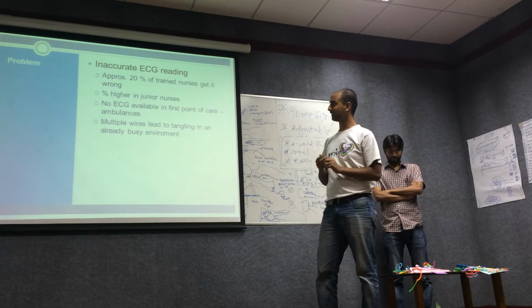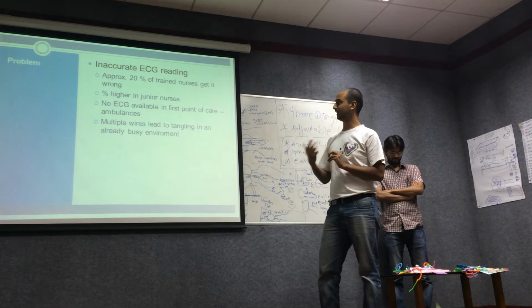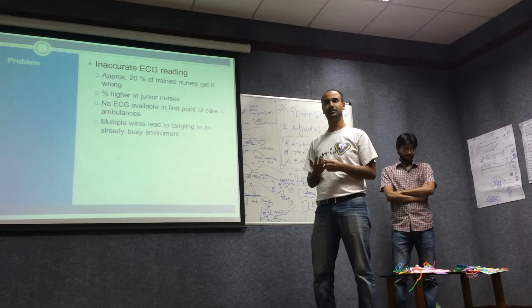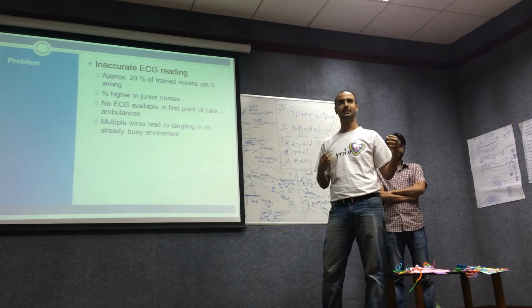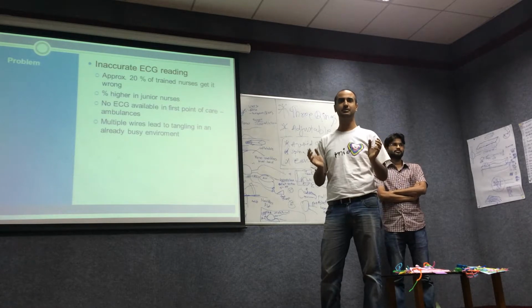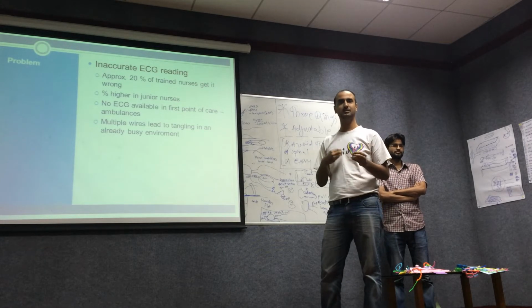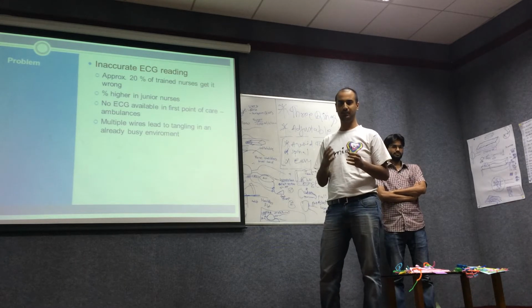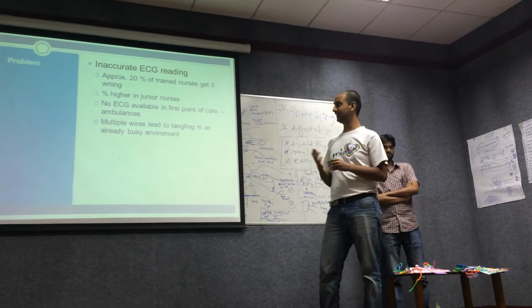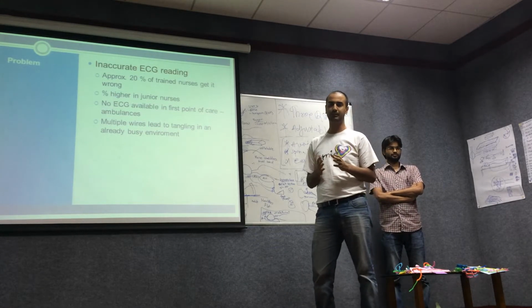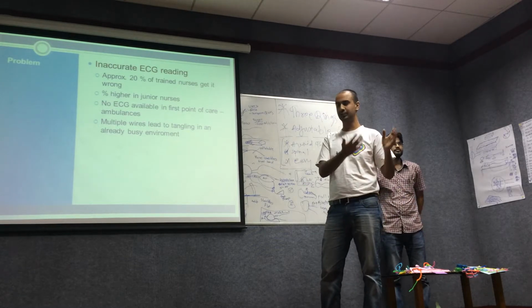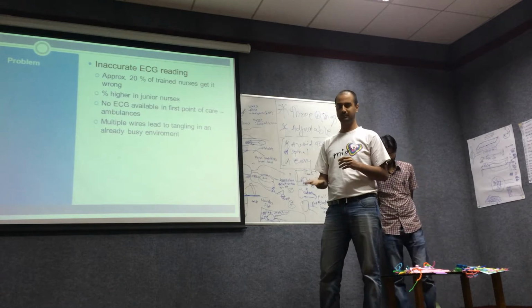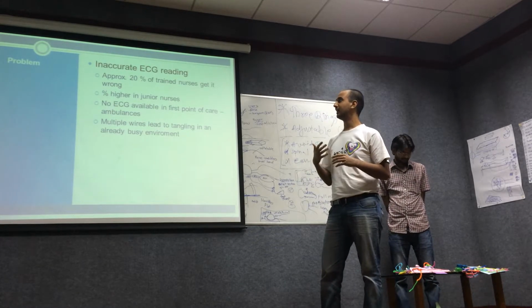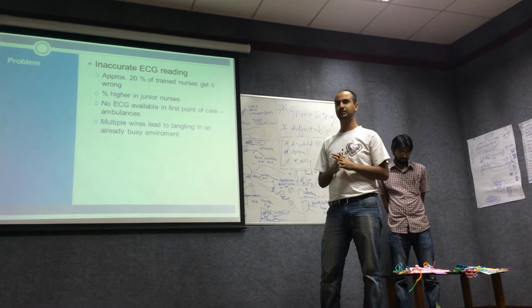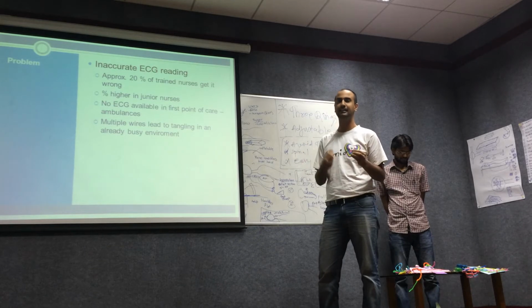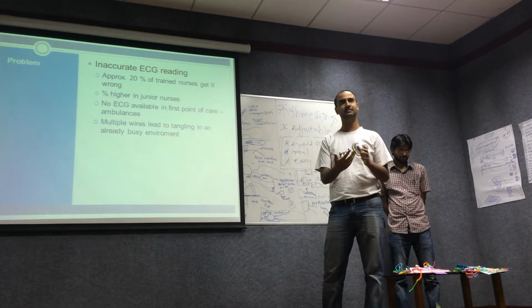Second thing is, mostly it is done by junior nurses, and as there are 10 electrodes and all have their individual wires coming to the monitor, there's a lot of tension in those wires, and even a slight movement of the patient can cause movement of the electrode, and hence the signal which you are really interested to capture may not be possible. Secondly, in a moving setup, for example, moving a patient from one OT to another, where he is continuously monitored for ECG, or in an ambulance, where there's continuous vibration and turbulence due to the motion, the conventional setup doesn't fit because of the way the electrodes are pushed and all these tangled wires, all these 10 wires going to the monitor.